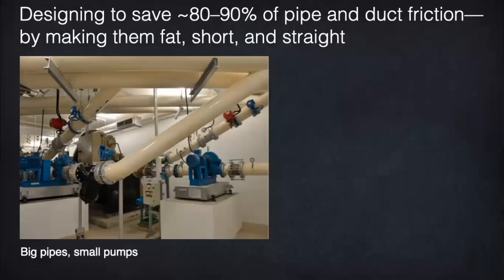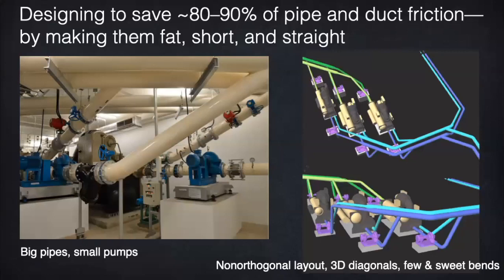So low friction pipes make the blue pump toward the right so tiny that it looks like a decimal point error. Notice also it's raised up to meet the pipe rather than conventionally dipping the pipe down to the floor to meet the pump and then back up again. Likewise, the 10 chillers that are normally in a neat row get staggered to eliminate the pipe elbows.